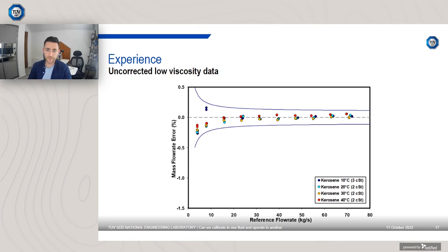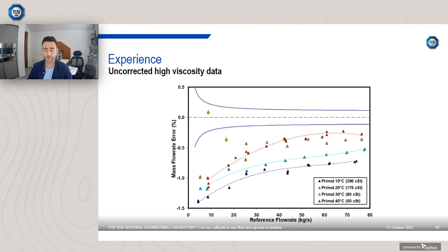You can see we've got the manufacturer specification, those dark blue lines. You can see that all the data sits nicely within the specification. You can actually see the deviation start to increase at the lower flow rates. That's potentially due to these zero effects, which are common with Coriolis flow meters. But this looks like a reasonably good calibration for all four temperatures, and we'd certainly be happy with that. Not even that much of a temperature effect either, which looks very, very good. Apologies. So the results look well within specification, so looks good.